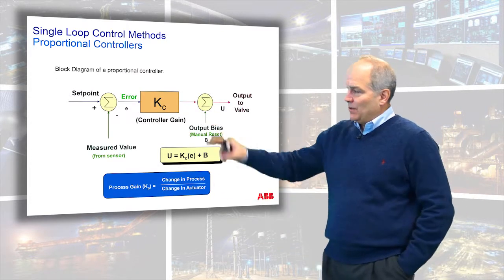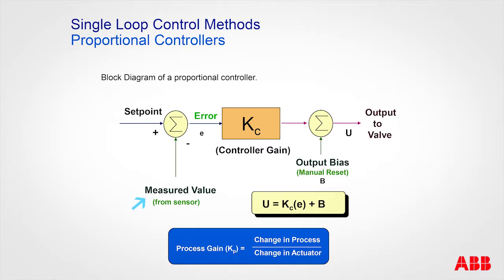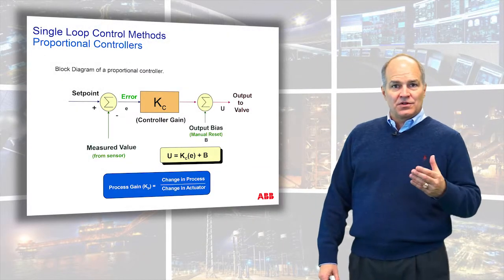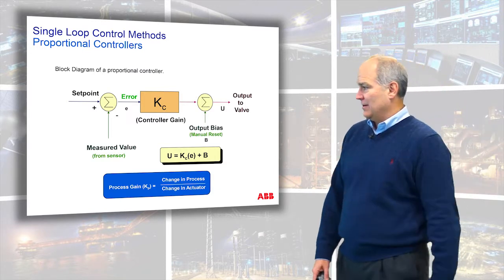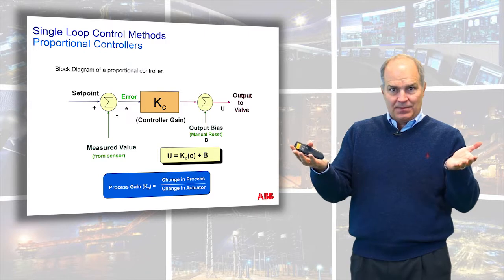In the simplest form, a block diagram shows a set point and a measured value; the difference is the error. The error is multiplied by a control gain, and that control gain times the error is the output that goes to the valve. In the early days there was actually a manual reset knob because proportional-only control results in an offset. The fulcrum analogy illustrates that the error is exactly proportional to the output.